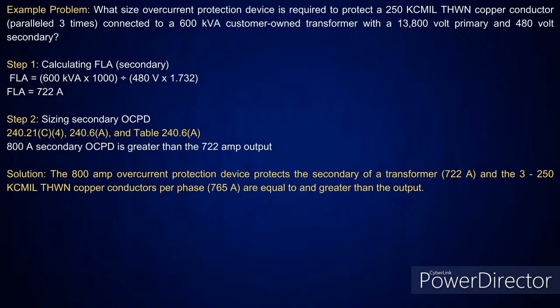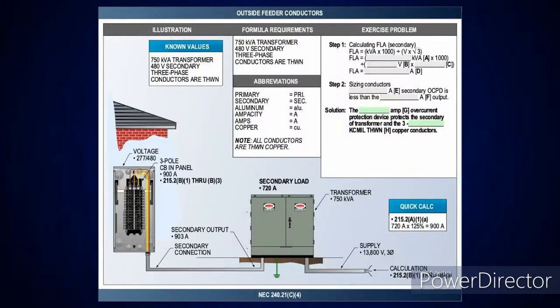That's what I'm saying. I'm doing transformer secondary conductors, but the calculation isn't hard. All you need to know is the kVA of the transformer, know what the voltage is on the secondary side, and then know if I'm not over 800 amps, I can go up. Once I'm over 800 amps, I have to drop down. It's that simple. So just so everyone knows, the only way the NEC applies is if that's customer owned. If that's utility owned, then the NEC doesn't apply.